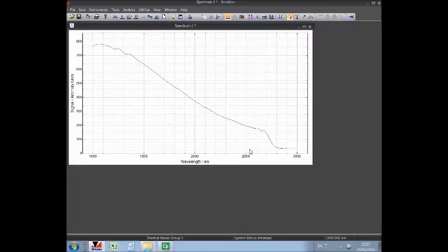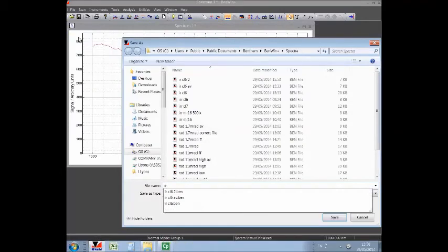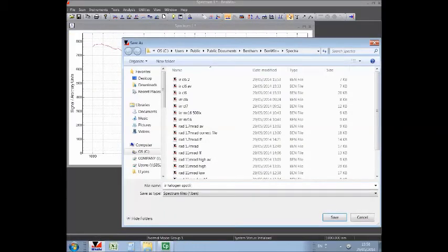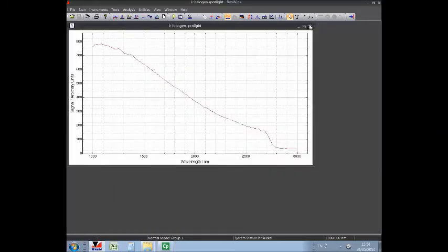We now have the measurement result showing a fairly typical response for this type of lamp. The relative shape of the source in the infrared shows some features perhaps due to the transmission of the glass front face of the source and attenuation in the long wavelength region. This is quite a different story from, for example, a dichroic, filter-based source, where you see swooping interference fringes throughout the scan range. We would, in the PSL Wizard, combine this scan with an absolute irradiance measurement of the source to perform analysis over the full range, 200 to 3000 nanometers. We will save this as the infrared of halogen spotlight, and that concludes the measurements here.